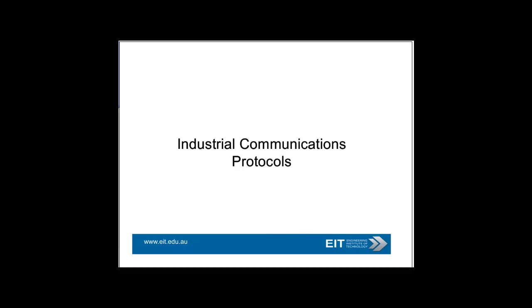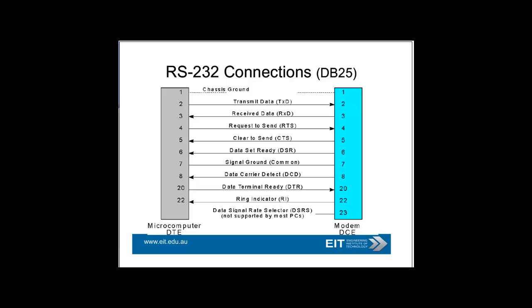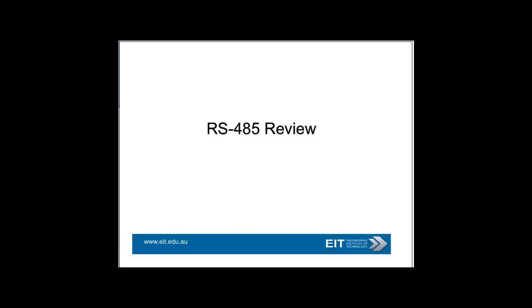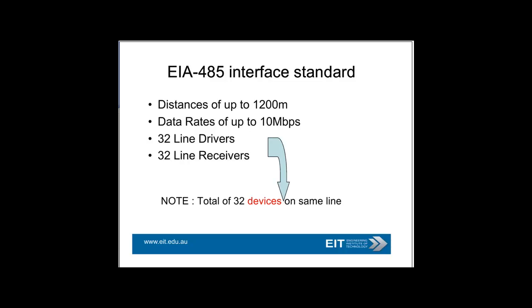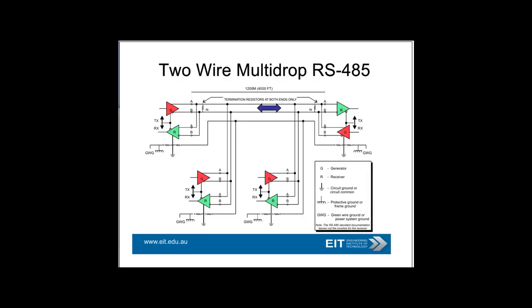Typical protocols and standards used are RS-232, which has probably been surpassed nowadays, RS-485, Modbus, and the DNP3 protocol. RS-232 and RS-485 are interface standards, not protocols as such. RS-485 is probably the key one — it's a balanced standard, so it's got extremely good noise immunity, going up to a kilometer and 10 megabits per second over a few meters. It supports 32 transmitters and receivers on the system and is very resistant to noise, making it very good quality. It's used for Profibus, for example, and a lot of RTUs and data acquisition units use RS-485.